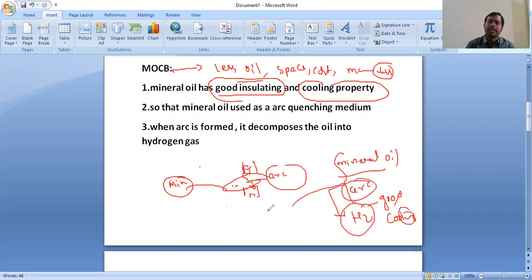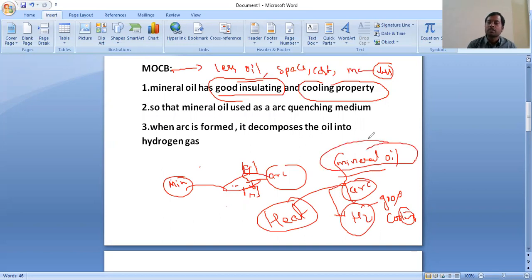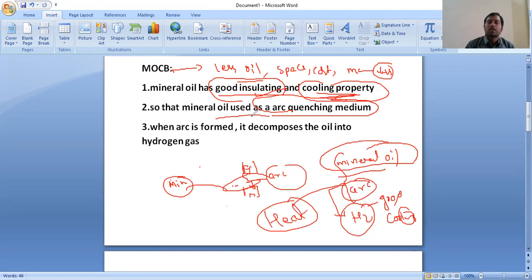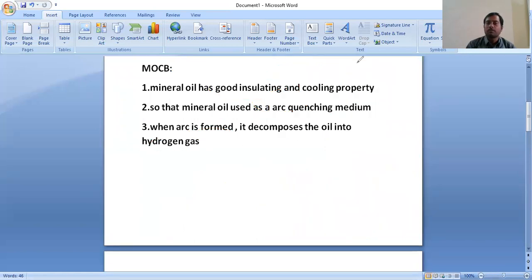Arc is nothing but more heat, so immediately we should reduce that heat. That's why mineral oil is used — it has good insulating properties and also cooling properties. Whenever the oil reacts with the arc, gas is formed, and that gas has good cooling properties. Mineral oil is used as an arc quenching medium. Arc quenching medium is nothing but arc extinguishing — this oil has arc extinguishing properties, so it is used to quench the arc. Quenching the arc means eliminating the arc. Whenever arc is formed, it decomposes the oil into hydrogen gas. The oil and arc reaction results in hydrogen gas.